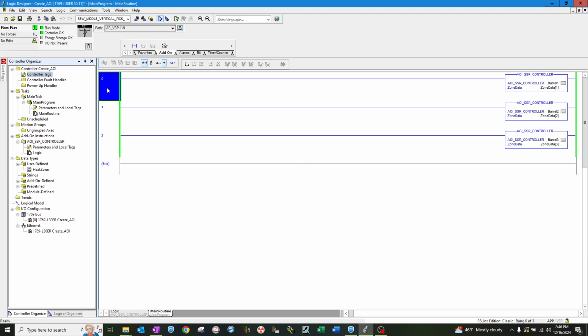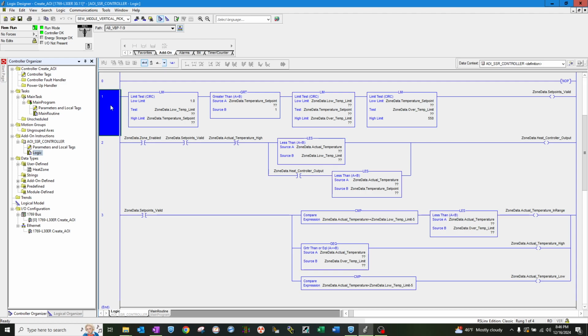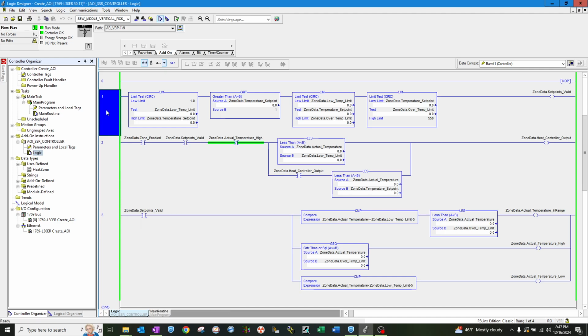Okay, and that's it. We tested the function in the first video of how the actual logic functions and also how to monitor this per the instance of the call. So if we wanted to just see barrel 3's code, we could. Or if we're having a problem with a set point, one good thing about this code, like I mentioned in the first video, is if you have a problem with this AOI, typically it affects them all. So it makes troubleshooting a bit easier to track down.